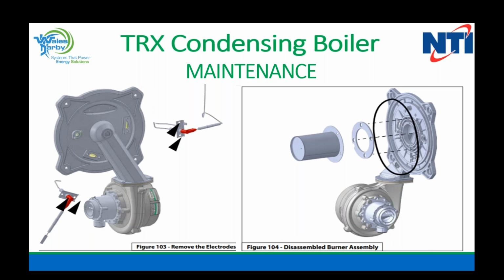So now we can pull out the igniters and inspect them if needed, but if at this point, on the left-hand side, everything looked good, everything was clean, you sprayed with your solvent, could be a simple green and water type of situation, you spray along the inside of the heat exchanger between the spacing on the pipings, and use a plastic brush. Scrub it down, rinse it out, make sure that the condensate drain is clear. If everything looks clear, you didn't see a lot of what would look like coffee grinds inside there or none at all, then you know your venting is spot on, everything is good. At this point, you can put it back together, check for any gas leaks or anything, and then start the system back up.